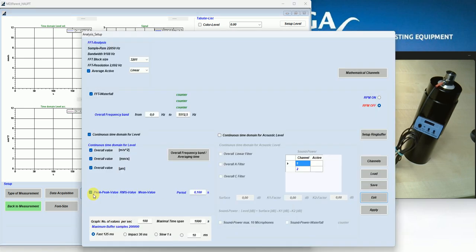In the Analysis menu, I can change or set up several properties like FFT line resolution, FFT averaging, linear or peak hold, or FFT waterfall analysis. If I want to determine a maximum peak value in the narrowband FFT during the measurement, then I need this option. Here I can get the overall values: the acceleration, the velocity, and the displacement in micrometers.